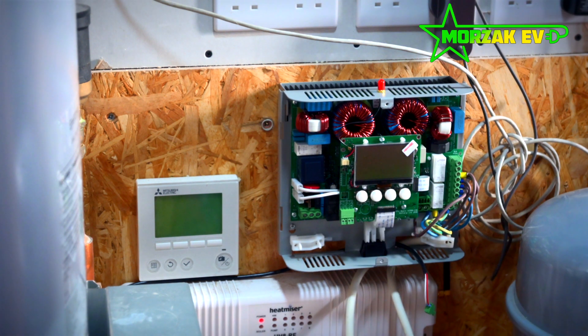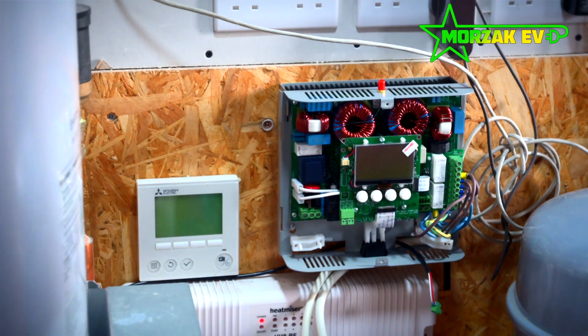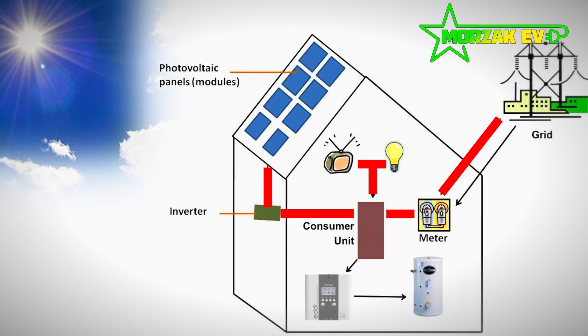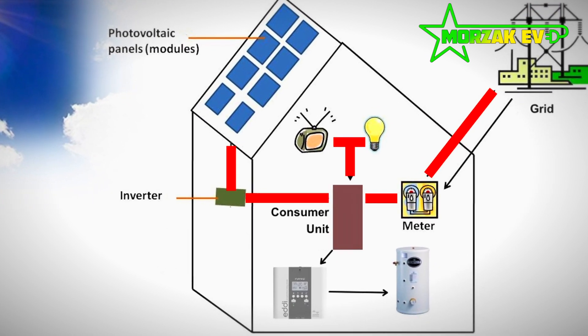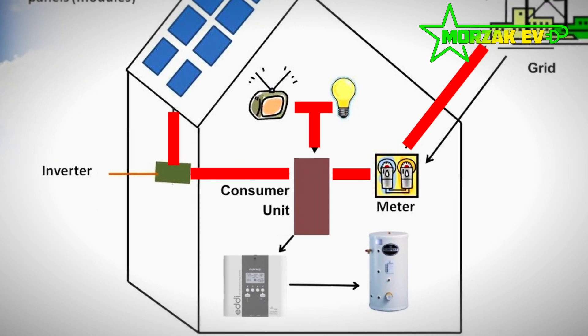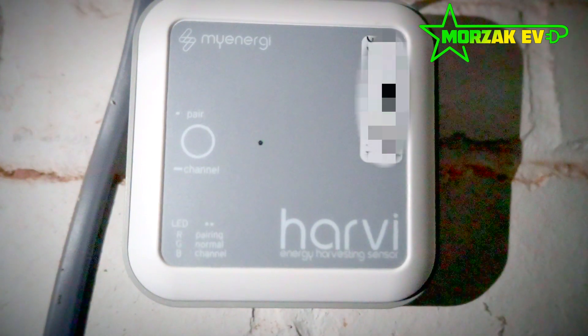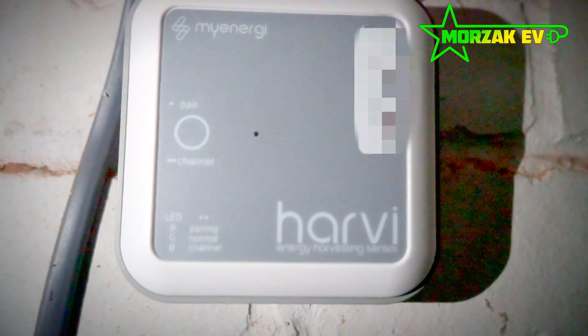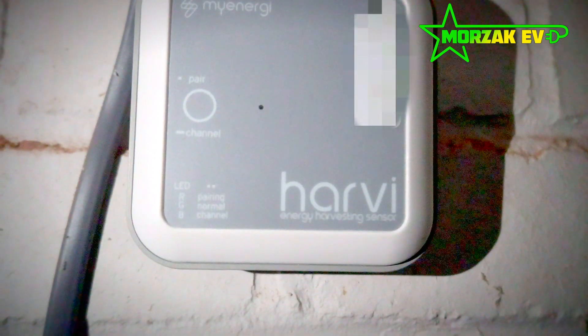Another detail to mention is that the CT clamps you put on your solar and your incoming main grid feed detect how much solar you're generating and how much you're exporting to the grid. If this isn't easy to hardwire into the eddi or the zappi, they also do the harvi, which sends a radio signal to tell the devices how much is being generated and how much is being exported.